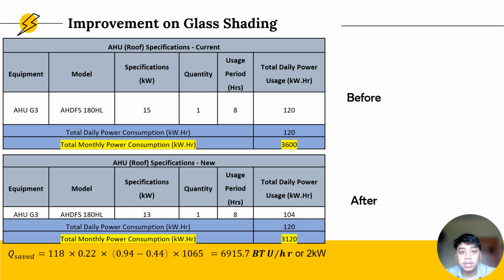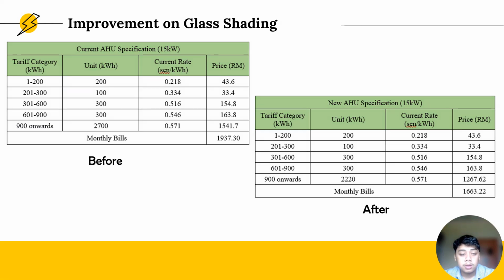By using the formula Q radiation equals solar heat gain factor times the cooling load factor times the shading coefficient times the window area, we can count the radiation. We can count the Q radiation for the saved one, which can be converted into 2 kilowatt. So we can have a total saving of RM274 per month and 3,288 ringgit per year.